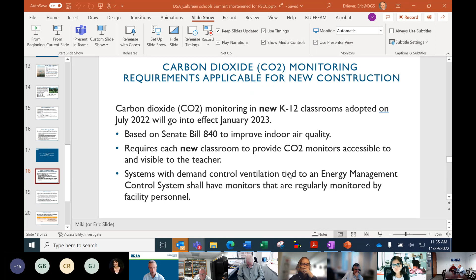And more specifically, it says each K-12 school classroom shall be equipped with carbon dioxide monitors that need to meet these 4 requirements. They're generally there in front of you, but tamper-proof, measure a minimum of at 15-minute intervals, and record those for 30 days, and need to measure at levels between the range of 400 parts per million and 2,000 parts per million or greater, and that they are certified by the manufacturer to be accurate within 75 parts per million at 1,000 parts per million, and require calibration no more than every 5 years. So those are some specific requirements.